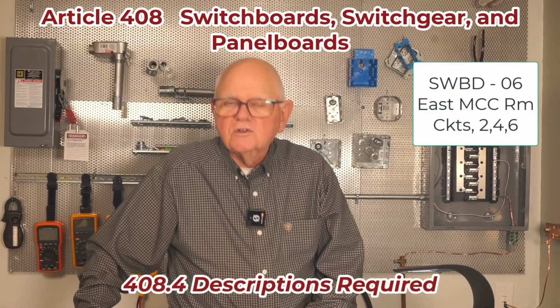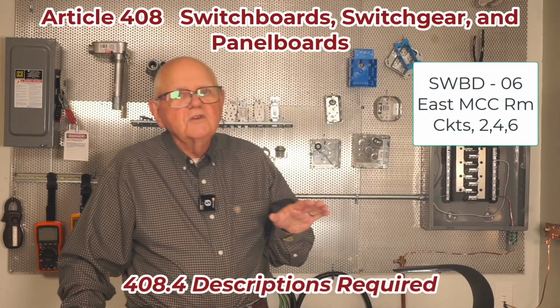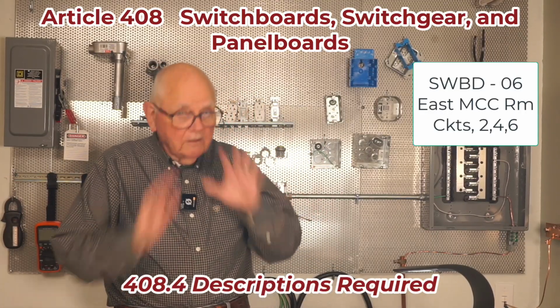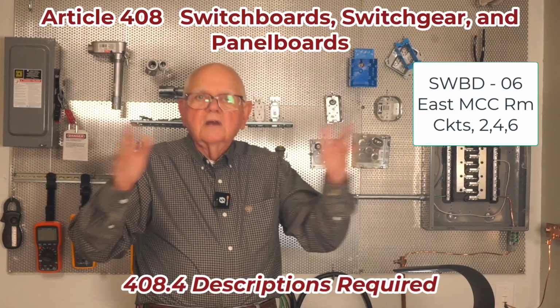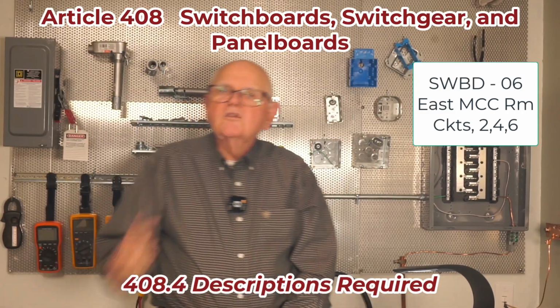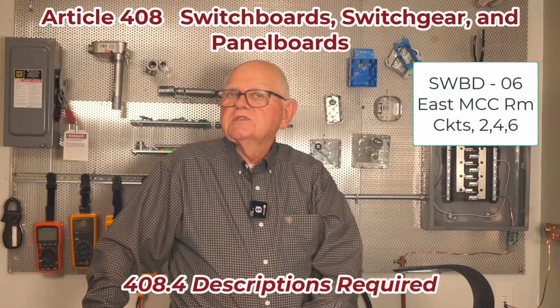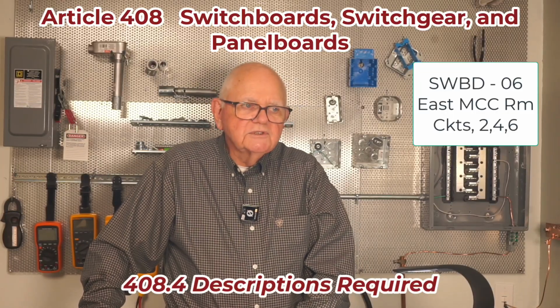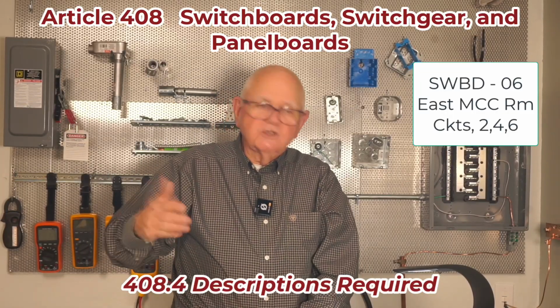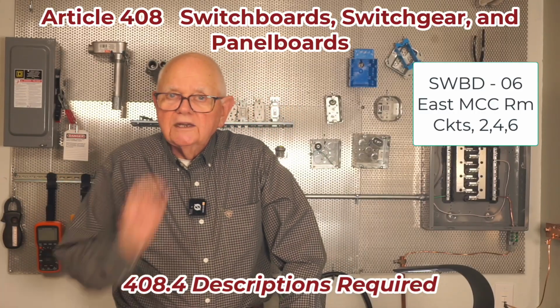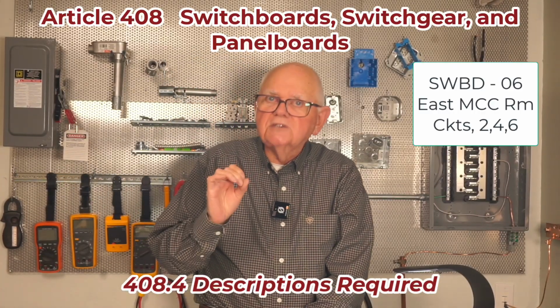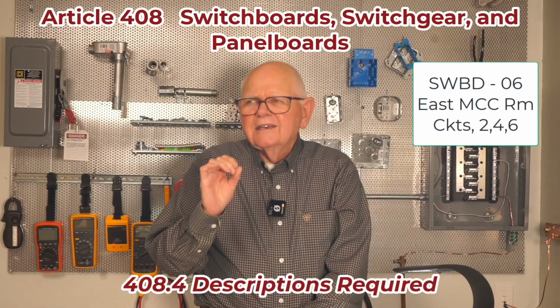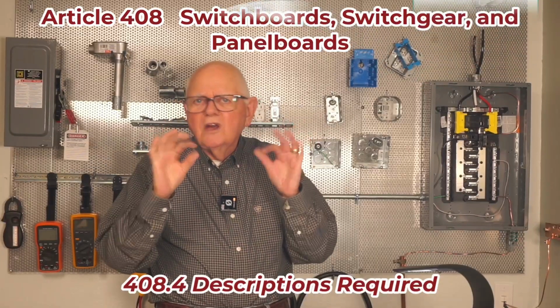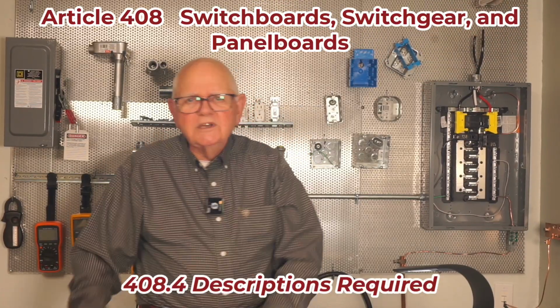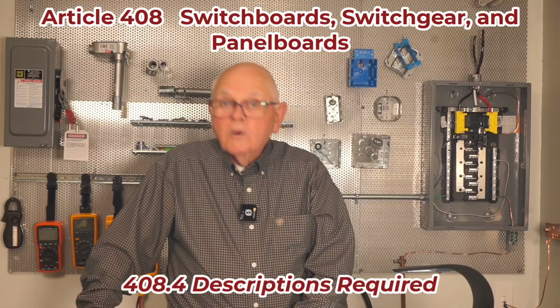408.4 says I have to put the source of my supply, in other than one and two family dwellings, on my panel boards: multifamily dwellings, commercial, industrial facilities, and so forth. I have to put the source of supply, and it has to be specific. It has to say, for instance, switchboard circuits 2, 4, and 6, something like that. So I need that specific information on there for the location of that equipment or that feed, and it's got to be permanent, meaning that putting a nice, pretty label on there that just sticks on with some adhesive is not permanent.